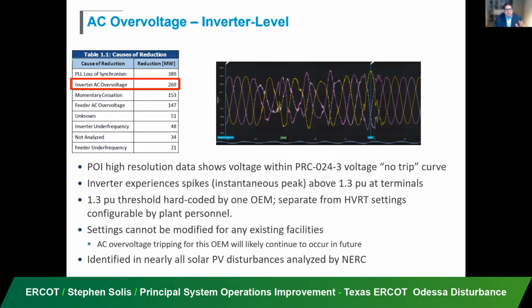This has been a persistent issue, once again seen in California, now in Texas. It's going to be very difficult to manage because the inverter is responding to the voltage it's seeing. And in some instances, it's even driving voltage higher when the system has already recovered. For example, the system sees the fault, recovers voltage, and is back within normal ranges, but the inverter is seeing a voltage that's still low, or it's actually injecting megavar when you wouldn't expect it to, driving the voltage higher at the terminal or the feeder level and tripping itself off.